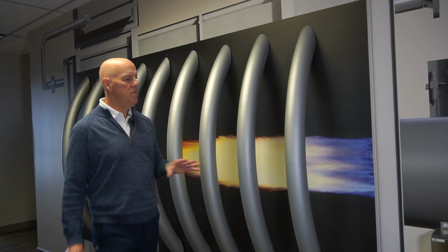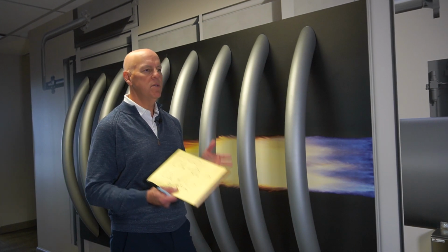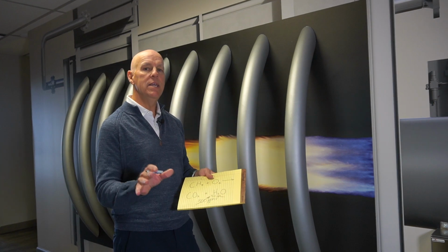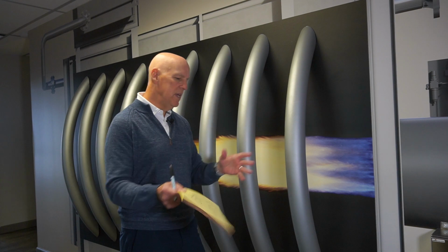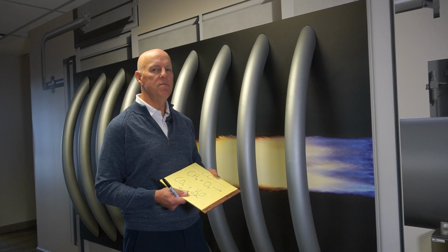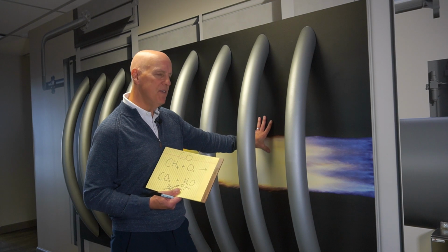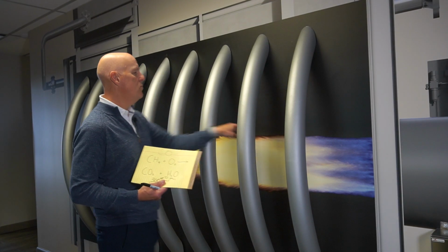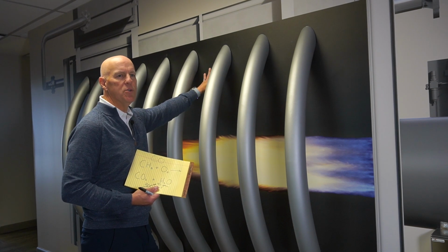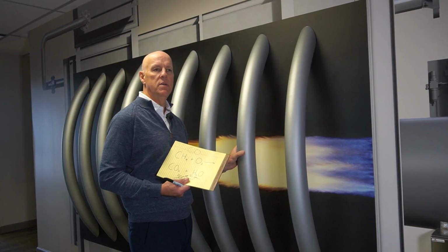But what happens is sometimes heaters are too big. When we design a heater, someone says, hey, we need 50 million BTUs per hour. So we design that heater for that size. Then they put the heater in, and they find out, well, we really don't need 50 million. We only need 15 million. Well, when it's sized for 50 but it's burning 15, guess what? What used to be 1400 degrees where my hand is is now 800 degrees, because there's way more heat transfer surface than I need.